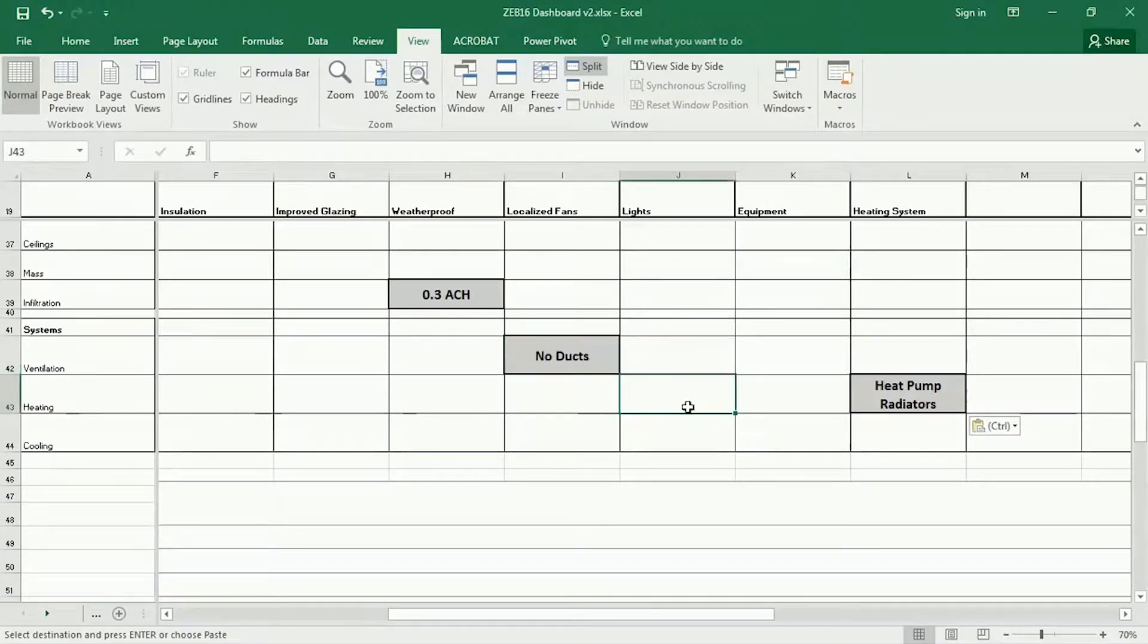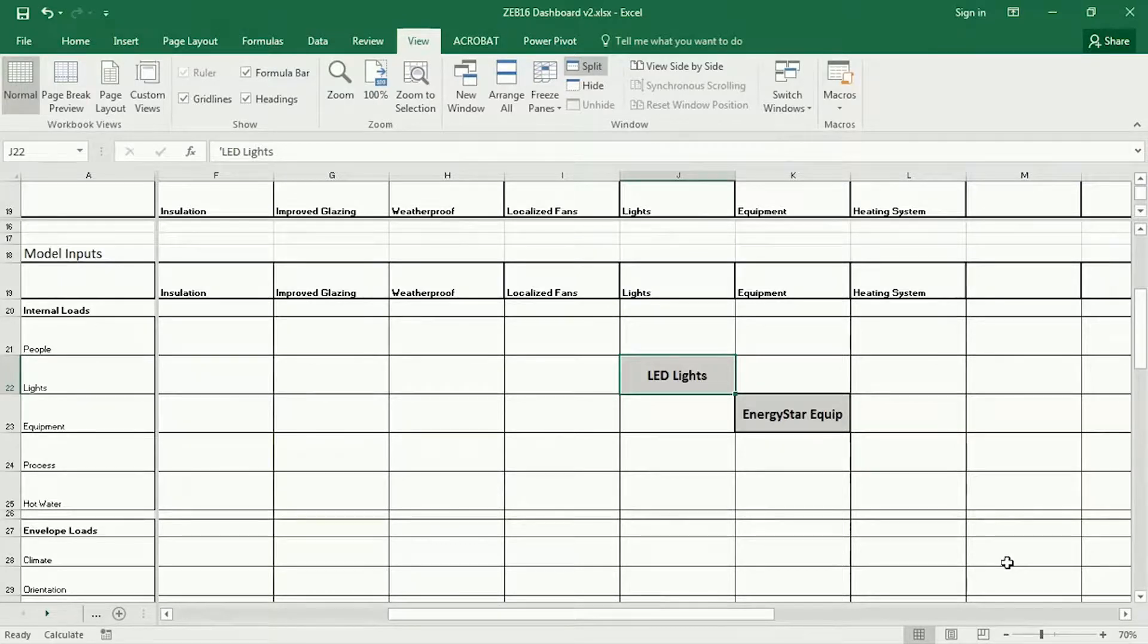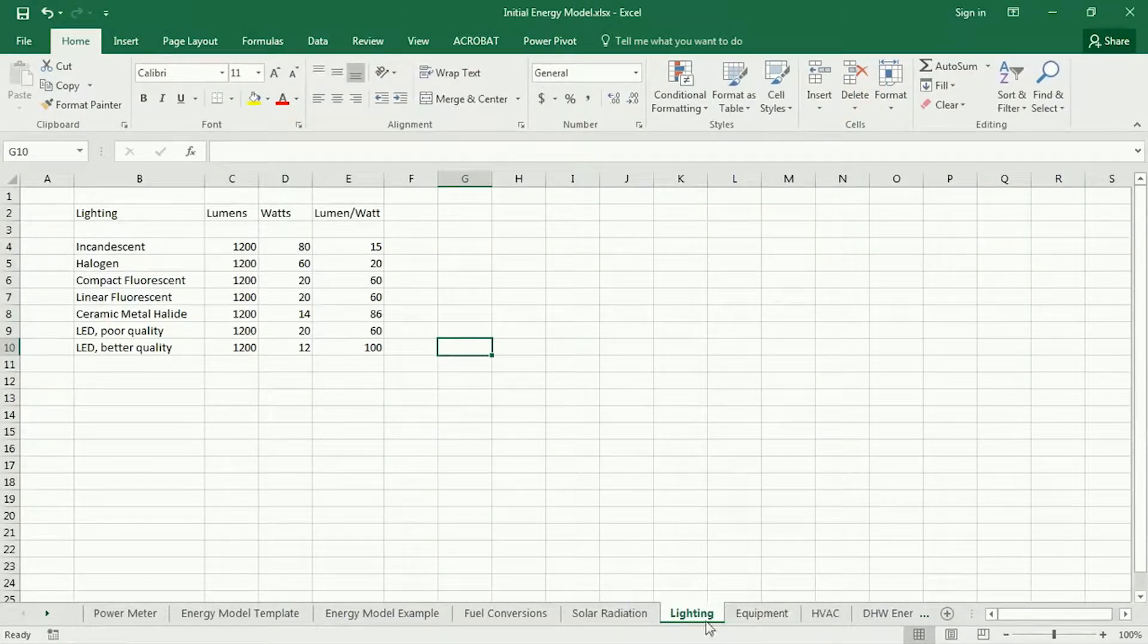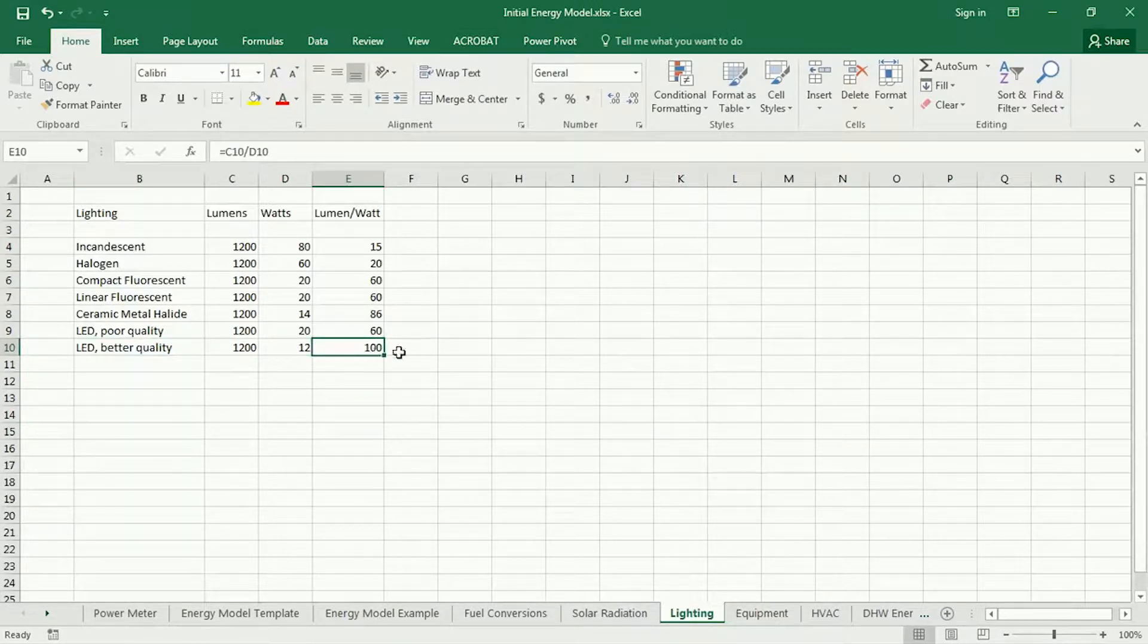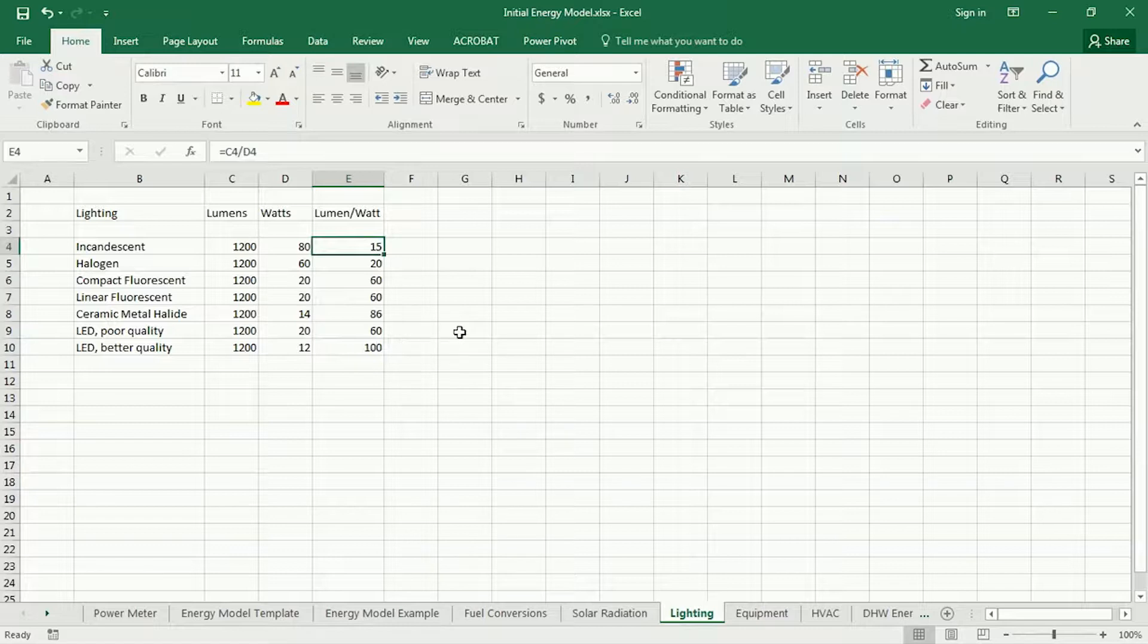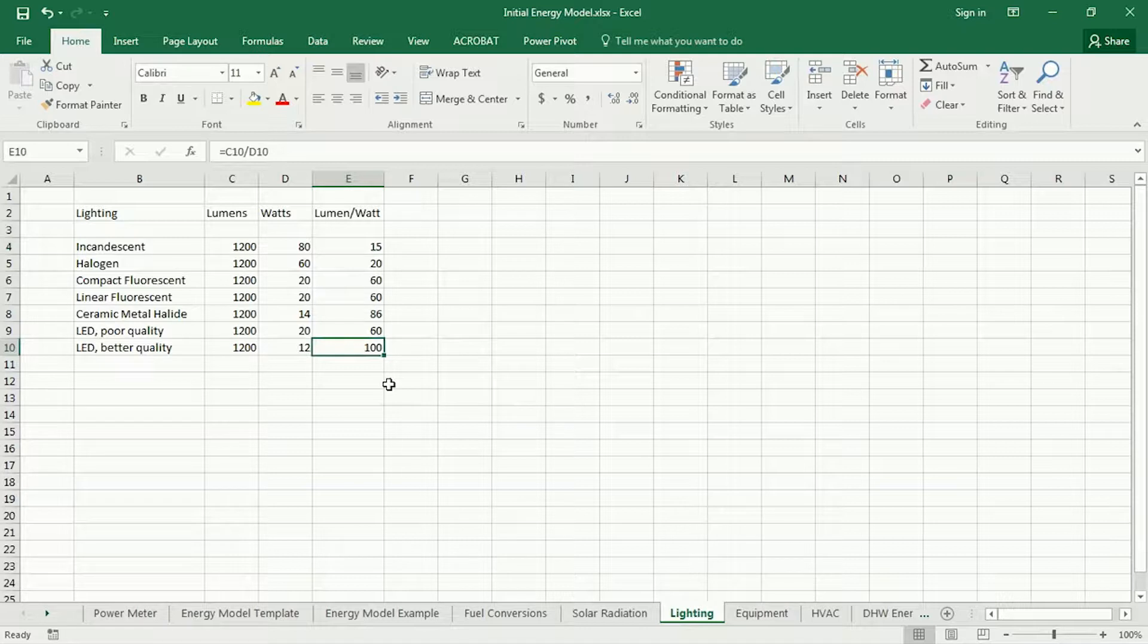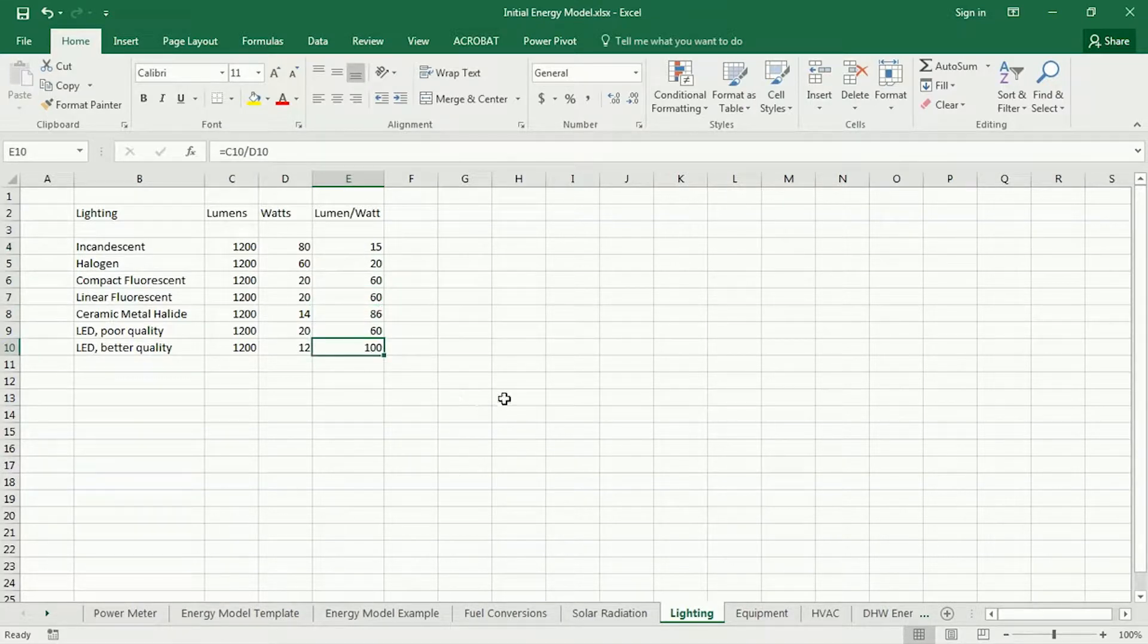And then back to the dashboard LED light. If you remember back to the initial energy model template, there was a tab here called lighting. And in this one, you can see the difference that LED lights would make. If you have good quality LED lights, it's about 100 lumens per watt. If you're replacing incandescent lighting, which is your standard sort of 100 watt light bulb, that is about six and a half times more efficient the LED is. In the case of Worcester, most of the lights in the computer lab are linear fluorescents. So it's only about 1.7 times more efficient going to LED.